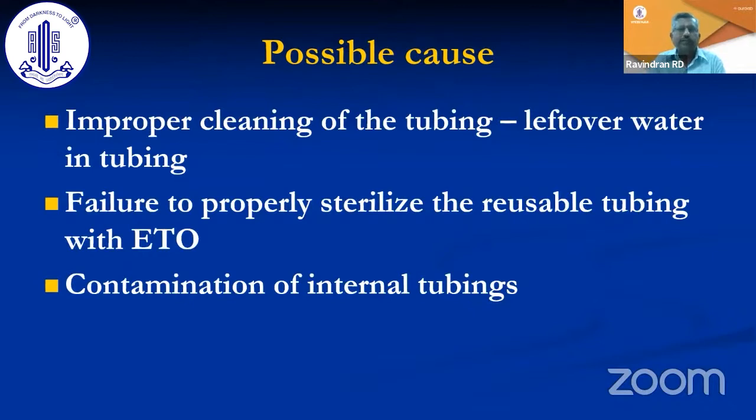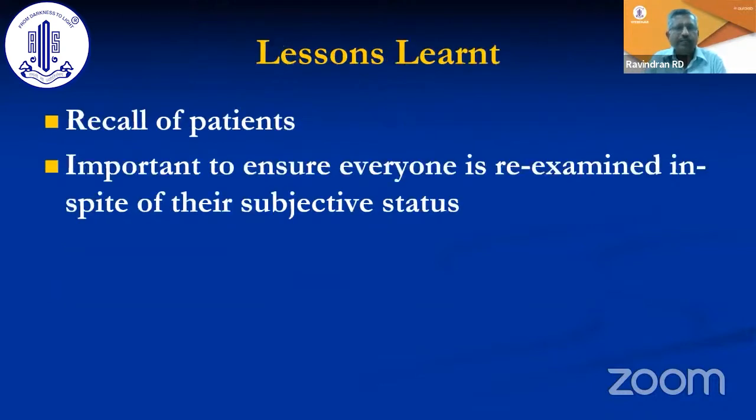This could possibly be because that was a time when we used to clean and reuse the phaco tubing. There could have been leftover water, the tubing was not completely dry, the cleaning was not appropriate, which means ETO may not properly sterilize such tubing. Or it could be due to contaminated internal tubing. We were not very sure which of these happened in this particular case.